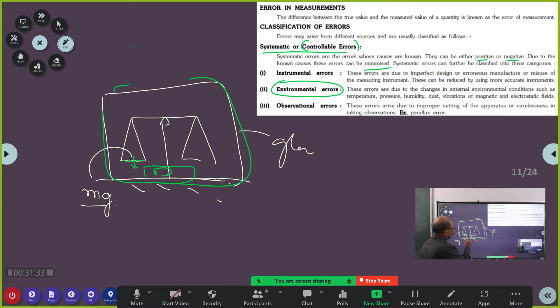And yes, these are very sensitive, and our breathing can affect it, so pressure can also have a bearing on this. And of course, humidity can play its own role. Dust particles can settle here or here, and if some more dust particles settle, then your weighing will be wrong. And of course, this is kept on a rubber padding, because if somebody is walking or some table is banging, this balance can get vibrations and so on and so forth.